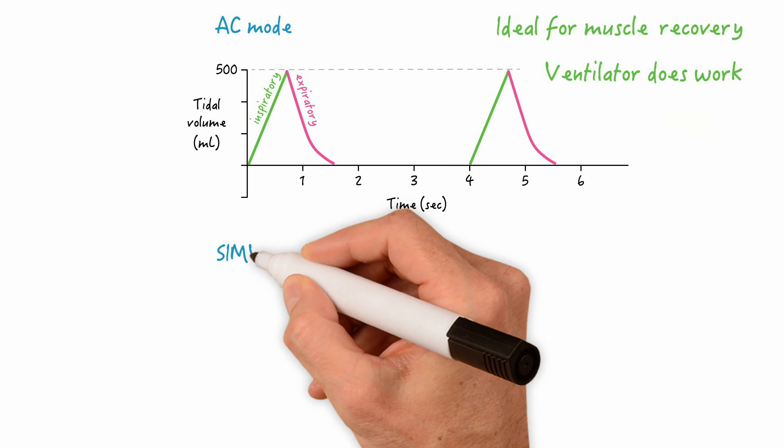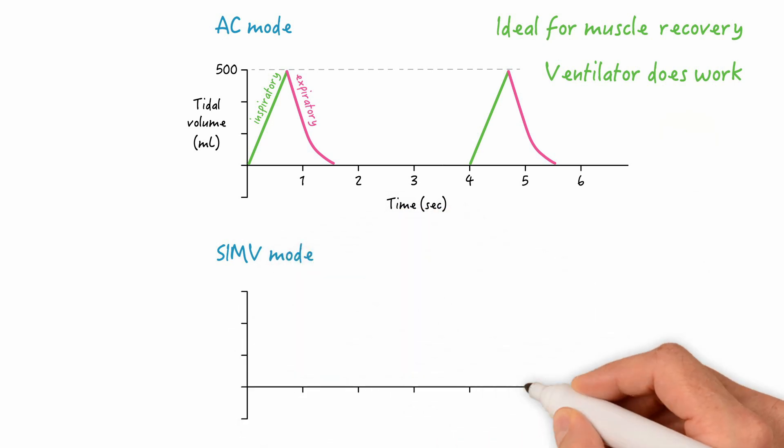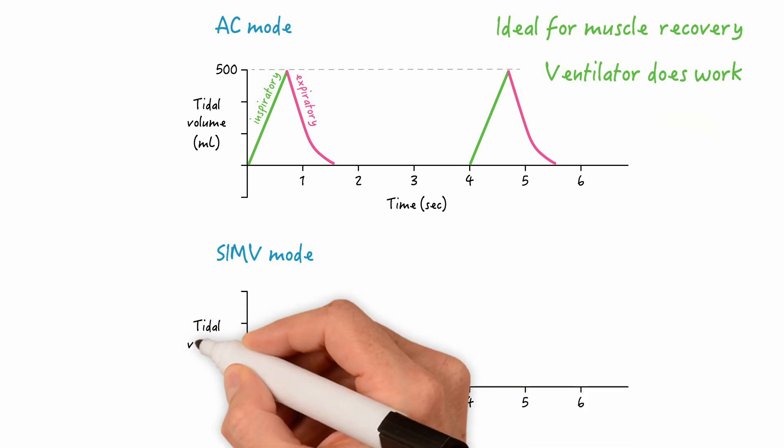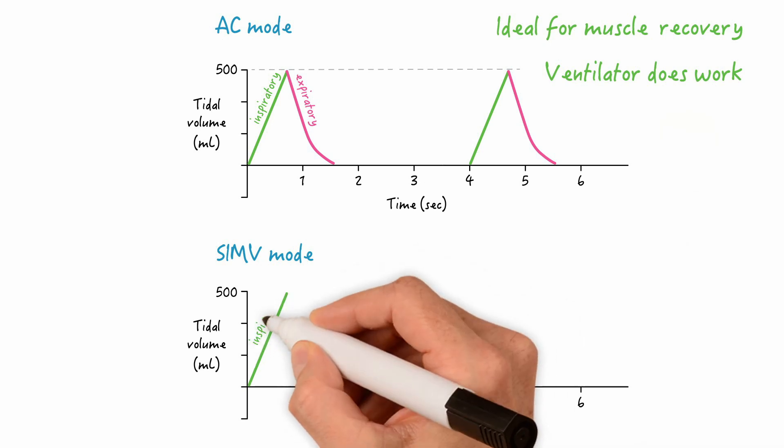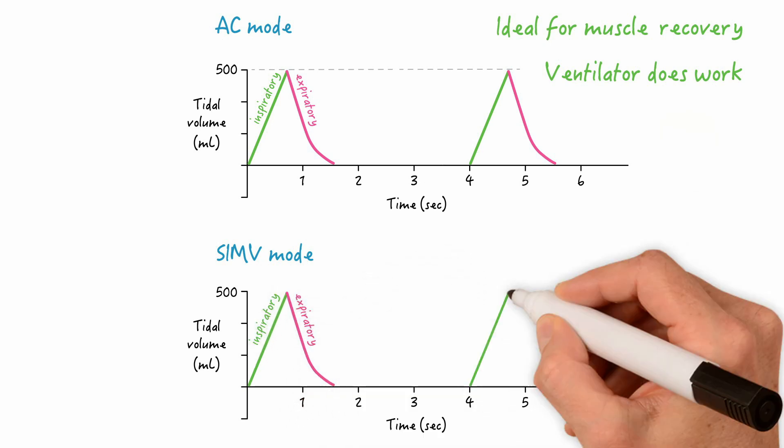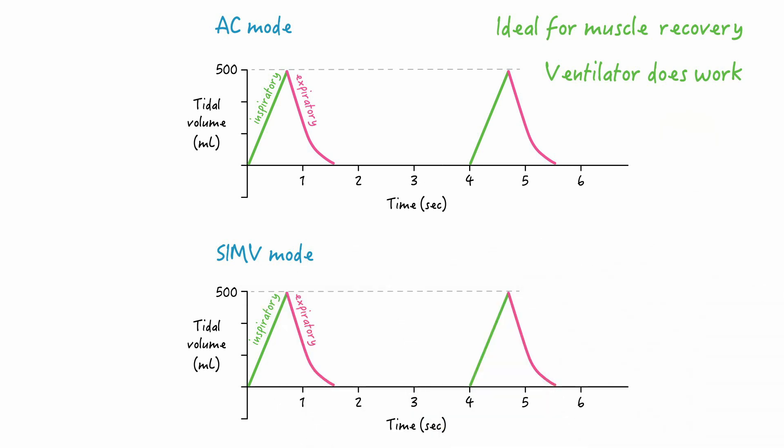So now let's compare this to the SIMV mode. In the SIMV mode, we can copy the same settings with a respiratory rate of 15 and a tidal volume of 500. And if you look closely, you'll see that a breath will be delivered every 4 seconds, just like in the AC mode. So you should be asking yourself this question: then what's the difference? Well, let's imagine what a patient-triggered breath would look like at the 2 second mark in both of these modes. And remember, initially, this patient most likely will not have adequate muscle strength since they probably have an acute ventilatory muscle dysfunction and fatigue.